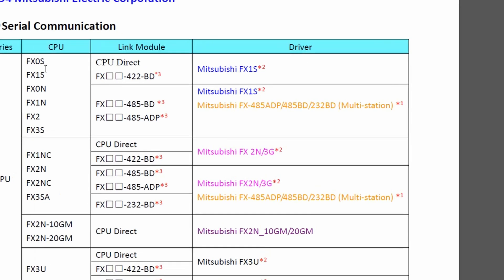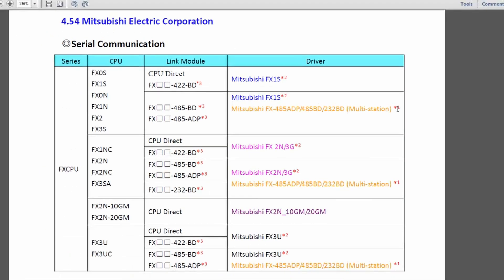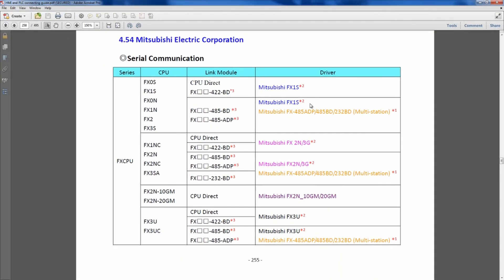What you'll do here is just find which CPU you're using. These are all the serial communicated PLCs. If there's a 2 here, a star and a 2, that means that it doesn't allow for multiple stations. But a 1 here will say it does allow for multiple stations. Something like RS-422, RS-485 for multi-drop. Anytime you see right here, it's only going to be connected to 1 HMI to 1 PLC. You can't multi-drop on it.